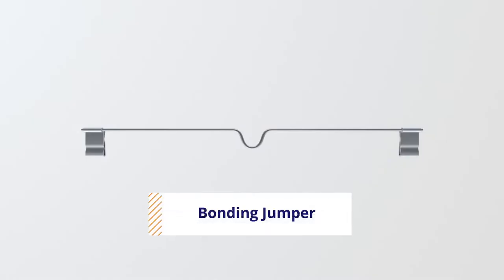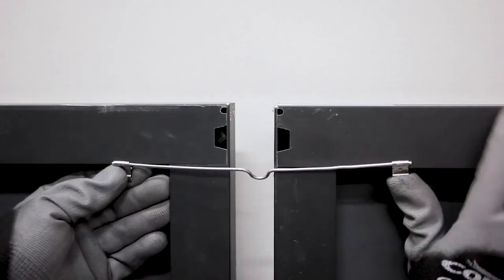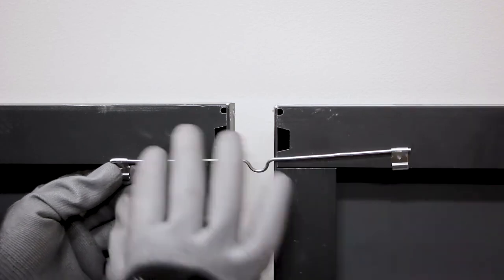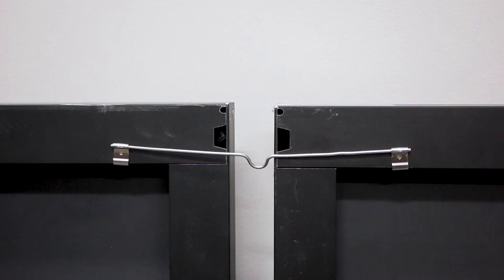One module jumper per row is used to carry the bond from row to row. To install the module jumper, slide the clip on one end of the jumper onto the flange of a single module in the row, and then slide the clip on the other end of the jumper onto the flange of the adjacent module in the next row.